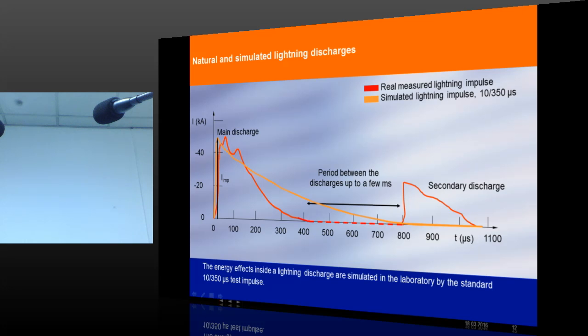You know, worldwide, when you want a surge protection device for the power incoming into a building, you imagine that in your house there is a power incoming distribution board and you want to buy a surge protection device for that incoming power supply. In the market, you can see surge arresters with 40K, 50K, 100K, 200K, 400K, 600K. But generally, nobody explains the shape. So, for the mains incoming panel, you need an SPD which is tested with 10 by 350 microseconds.